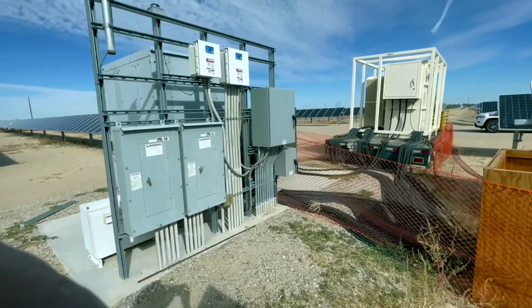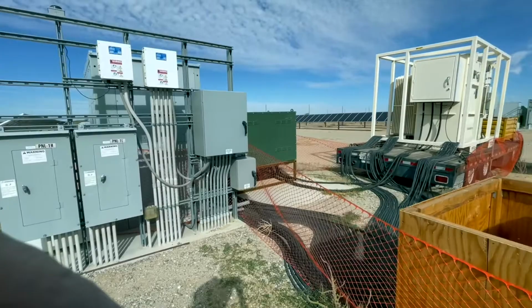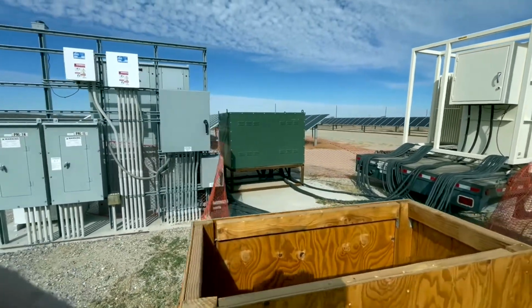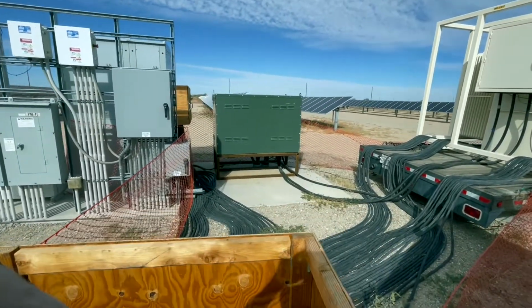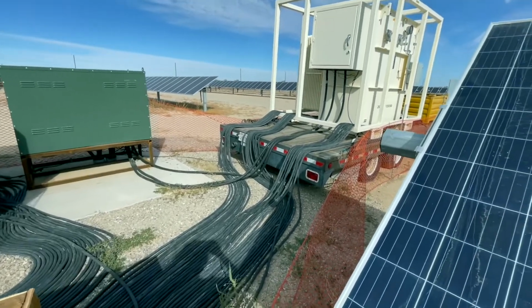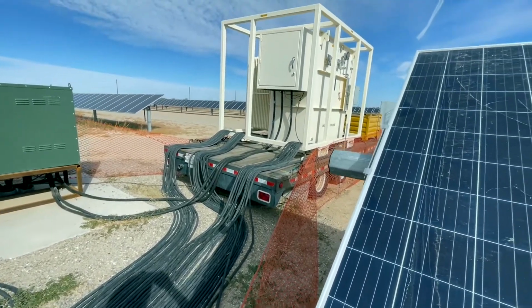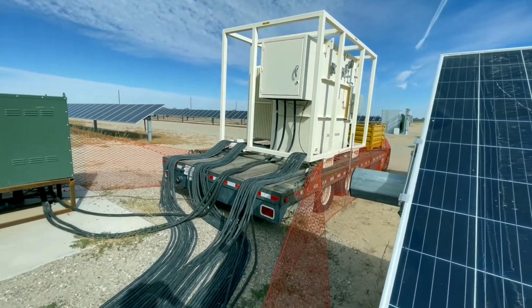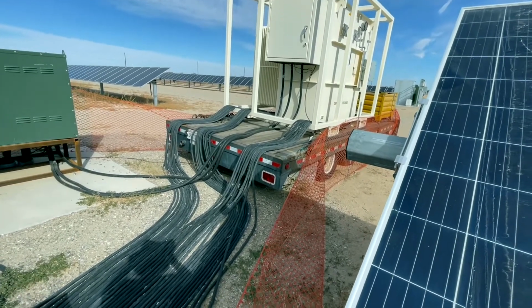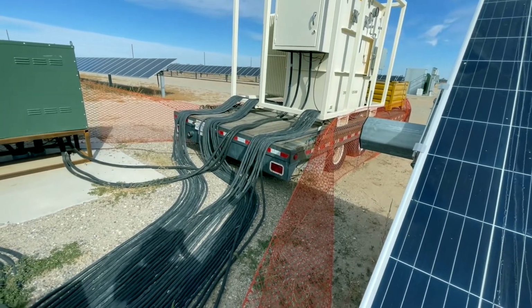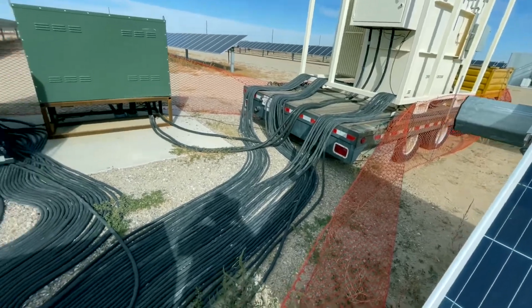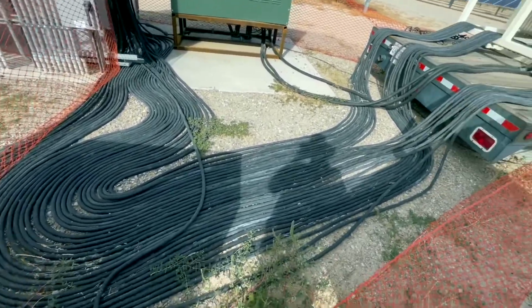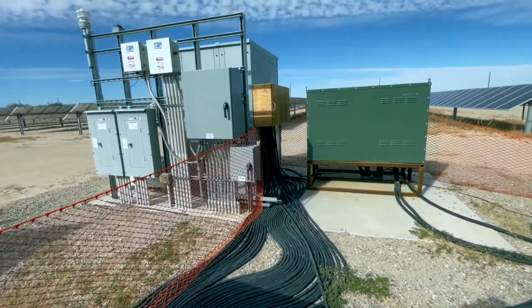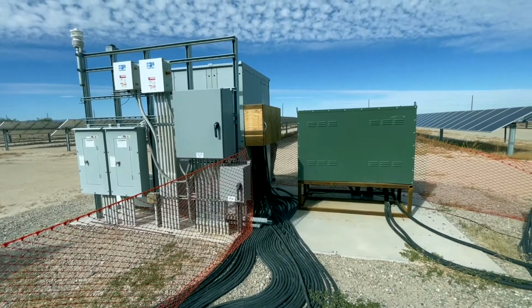Right where that green box is now is where our old transformer pad used to be. You can see the cables that come out of this temporary transformer. There's 10 conductors for each of the 3 phases, and 10 conductors for the neutral. They go in right here, into that plywood box, and that's our switch gear.